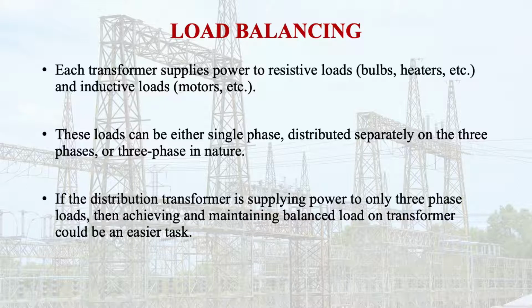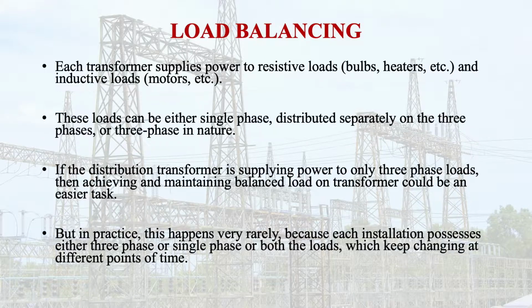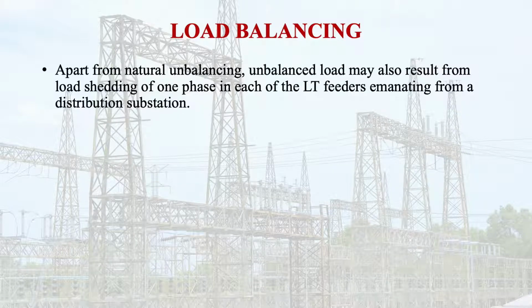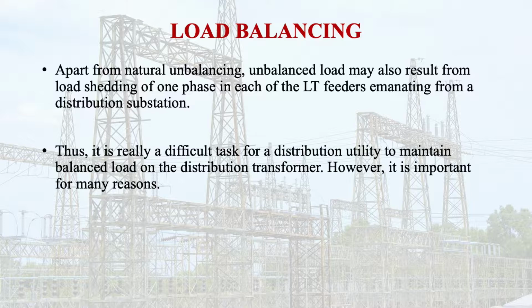So if the distribution transformer is supplying power to only three phase loads, then achieving and maintaining a balanced load on the transformer could be an easier task. But in practice, it does not happen. In practice, this happens very rarely, because each installation, either three phase or single phase or both, will keep changing at different points of time. So apart from the natural unbalancing, unbalanced load may also result from load shedding of one phase in each of the low tension feeders emanating from the distribution substation. Thus it is really a difficult task for a distribution utility to maintain a balanced load on a distribution transformer, because it is directly connected to the consumer, and consumer load may keep changing.